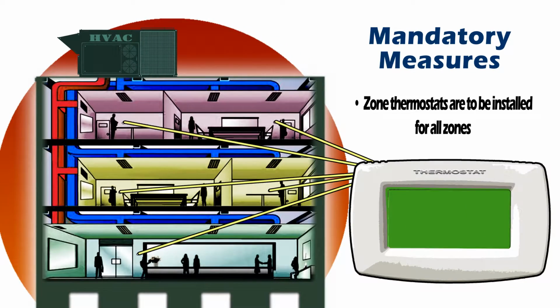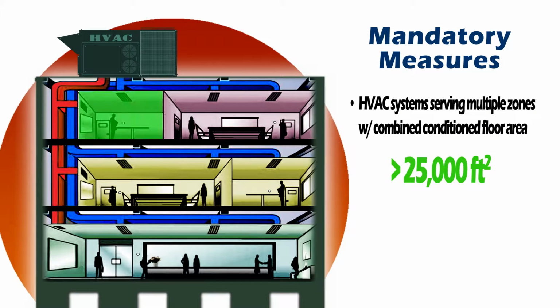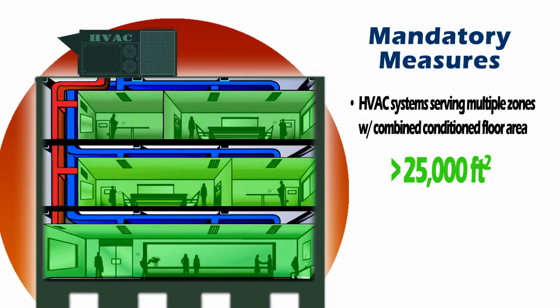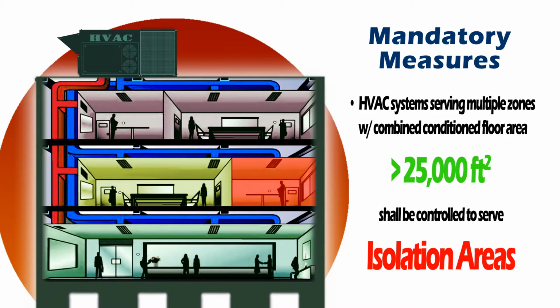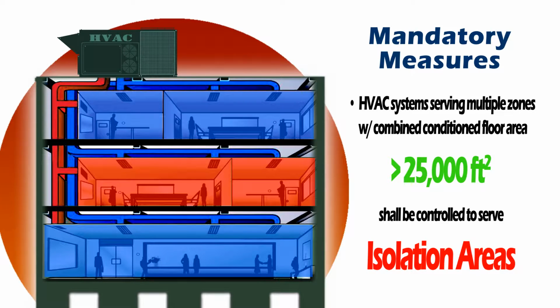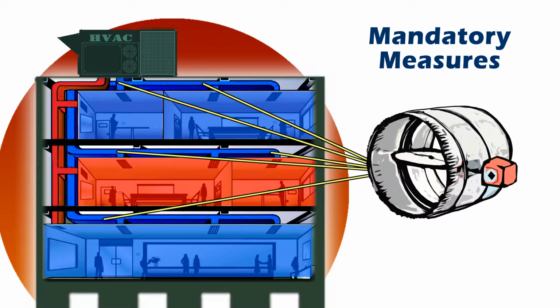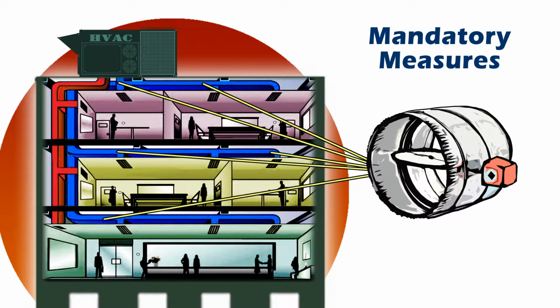Next, zone thermostats are to be installed for all zones and have the capability to set back the zone heating set point to 55 degrees or lower and set up the zone cooling set point to 85 degrees or higher, and include the capability for a 5-degree deadband for all zones. Each HVAC system serving multiple zones with a combined conditioned floor area of greater than 25,000 square feet shall be controlled to serve isolation areas. An isolation area is a room, group of rooms, or other area that has its own thermostat. Each isolation area shall be provided with valves and dampers to reduce or shut off the supply of heating or cooling independently of other isolation zones.